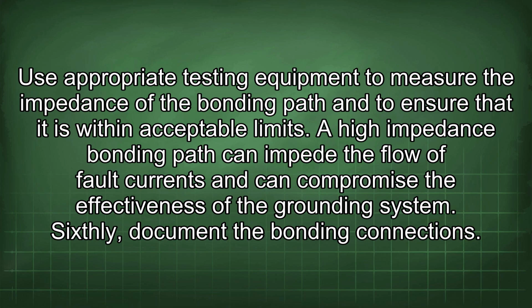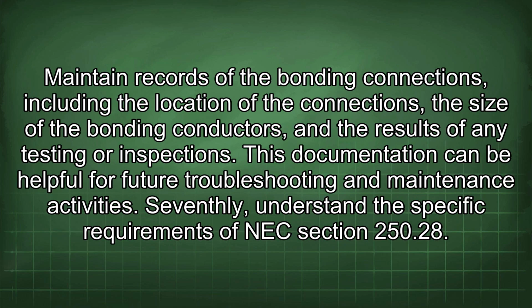Sixthly, document the bonding connections. Maintain records of the bonding connections, including the location of the connections, the size of the bonding conductors, and the results of any testing or inspections. This documentation can be helpful for future troubleshooting and maintenance activities.